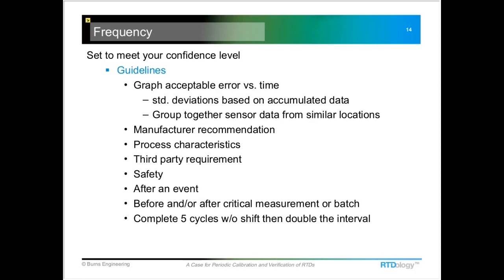So more about frequency here, just to reiterate some of the guidelines: manufacturer recommendations, your process or third-party requirements, safety, a particular event, and maybe the process value or the product value. If we go all the way through these, and let's say you picked 2 months as your first guideline for frequency, if you go through 5 of those cycles and nothing changes, then you can increase that to 4 months. Work the same for 6 months, and then you could double it to 12 months. That's probably a little more typical.